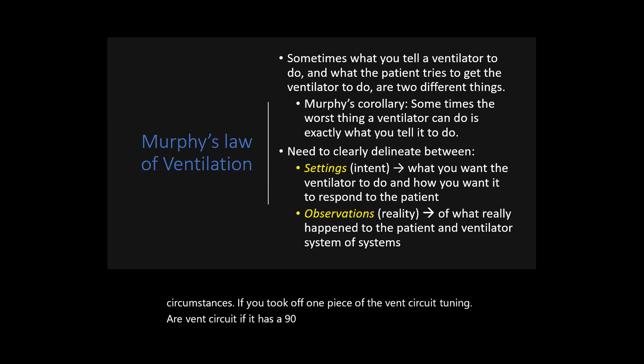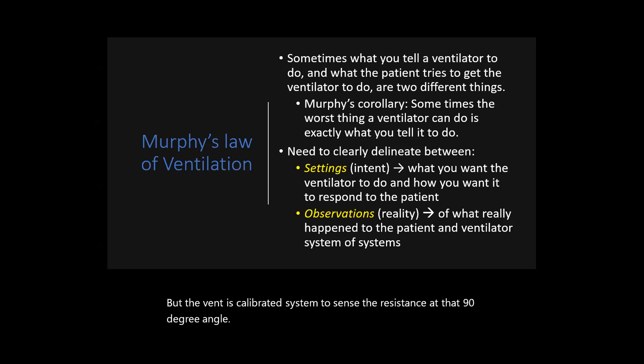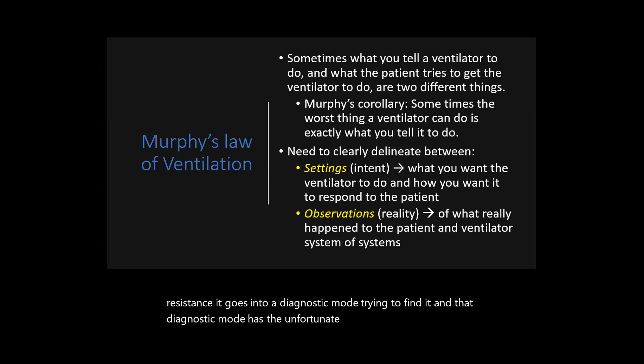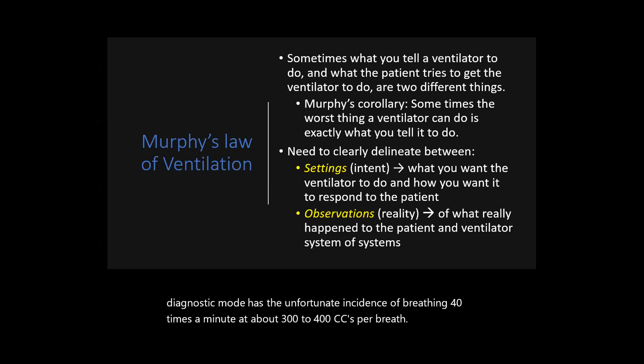But the vent is calibrated to sense the resistance at that 90-degree angle, just through the air pressure it sends down. If it doesn't sense that resistance, it goes into a diagnostic mode trying to find it. And that diagnostic mode has the unfortunate tendency of breathing 40 times a minute at about 300 to 400 cc's per breath. Would that kill a patient?